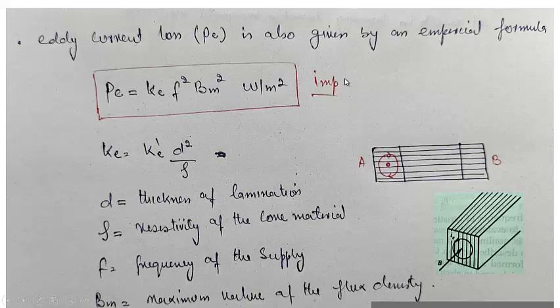Now this is an important formula, and we will be using it time and again, as I told you for the formula for the hysteresis loss. Here Ke is the property of the material, given by Ke dash d squared by the resistivity rho. d is the thickness of the lamination. Usually you will see that the core is not made of a solid piece, it is made of small thinner laminations. These thinner laminations are used to reduce the eddy current losses. You can see the direction of the eddy currents like this. So the current has to cross these lines, and these lines are insulated from each other.